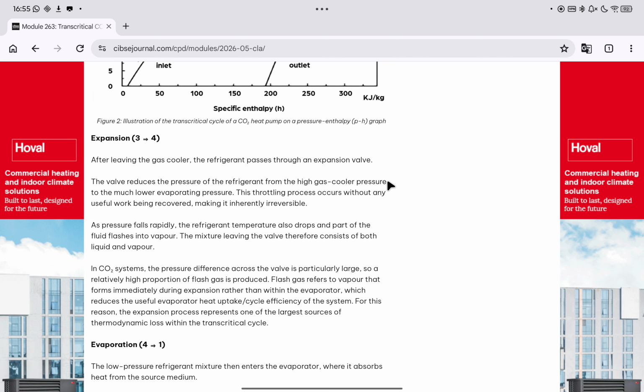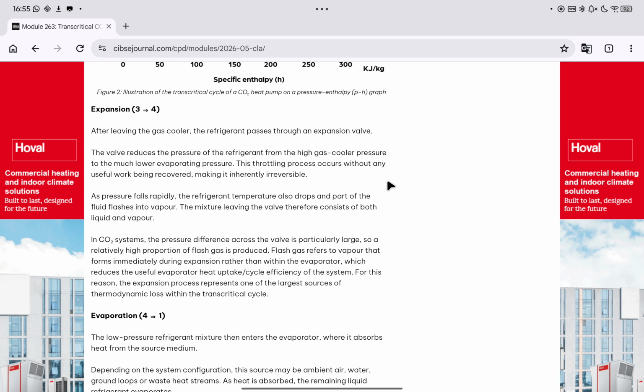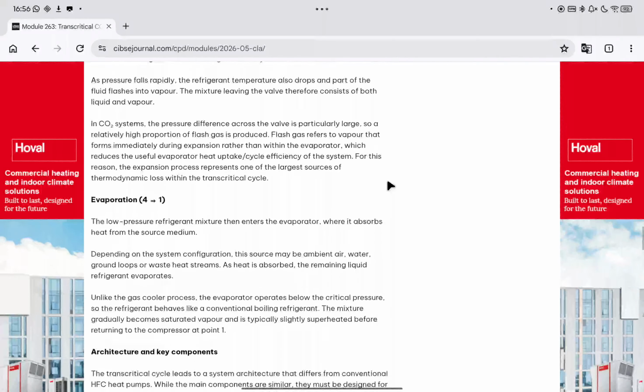In CO2 systems, the pressure difference across the valve is particularly large, so a relatively high proportion of flash gas is produced. Flash gas refers to vapor that forms immediately during the expansion rather than within the evaporator, which reduces the useful evaporator heat uptake and the cycle efficiency of the system. For this reason, the expansion process represents one of the largest sources of thermodynamic loss within the transcritical cycle.